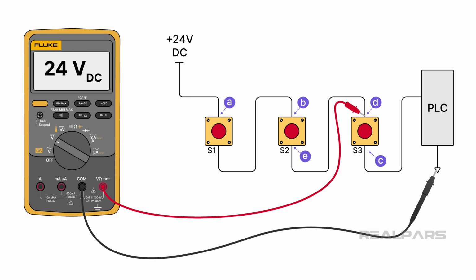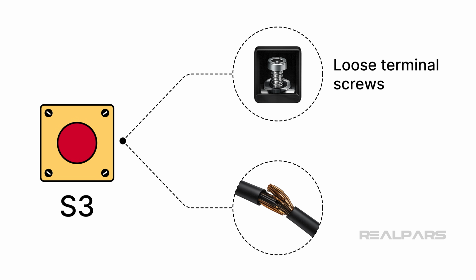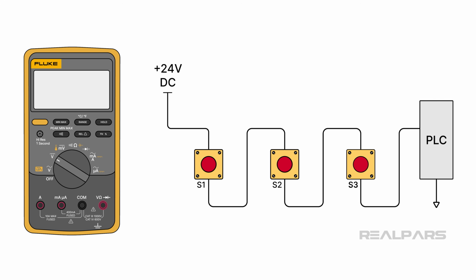Wait a minute though. Before replacing the switch, inspect the terminals carefully. Loose terminal screws and broken conductors are common culprits as well. But why don't we perform a final conclusive test on S3 using our DMM set to measure ohms? Why didn't we start with resistance measurements? Ohm meter measurements require that you remove power and isolate the component under test. Power removal is usually easy, but isolating the component sometimes involves difficult wire disconnections. Live circuit testing is easier and just as conclusive as resistance testing.